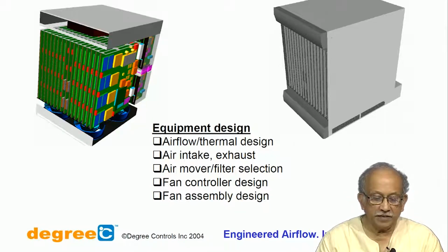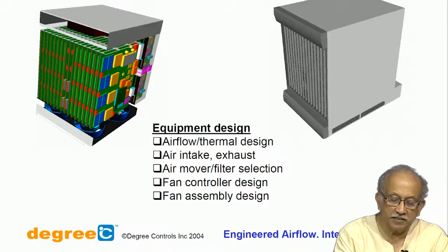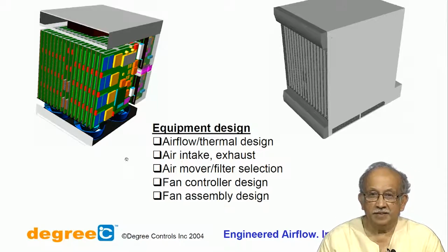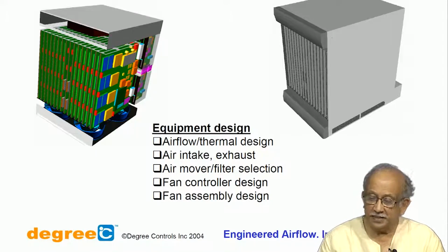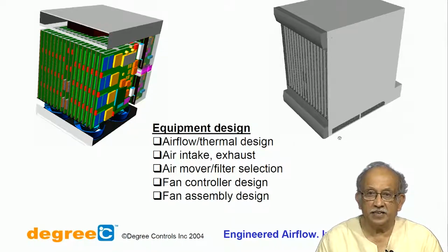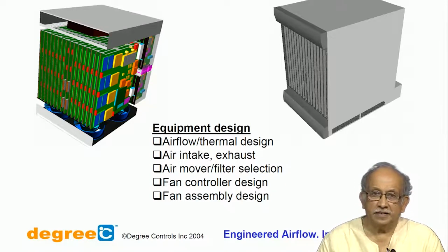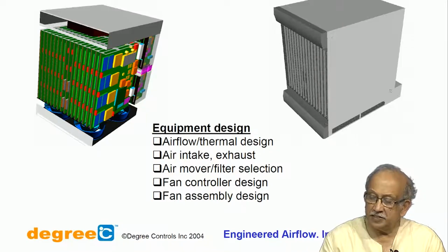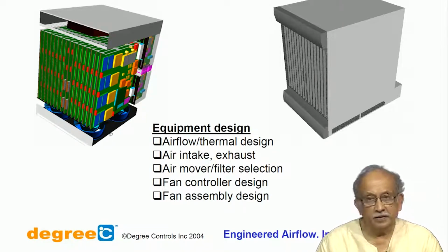If you remember, I have remarked to you earlier, you see here very conveniently, you can see you have these 4 openings here at the bottom. You see the blue colored thing? There is the opening, you are trying to take it out, and then at the top they have made some way of exhausting things. So, anything which you keep close to the ground, whether you like it or not, there is dust. So, it also acts like a very good vacuum cleaner, and the more the velocity is, or even if it is low velocity, the more the pressure buildup is, chances are these things will start picking up dust from outside.